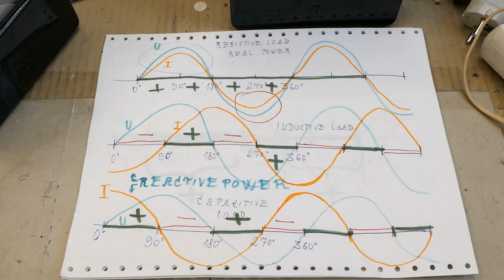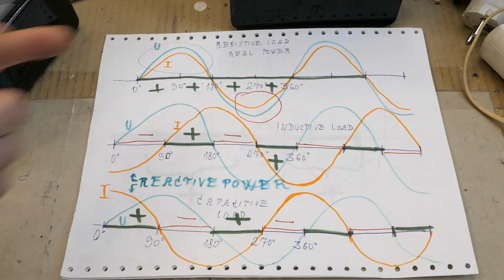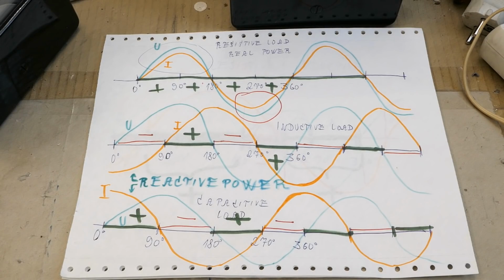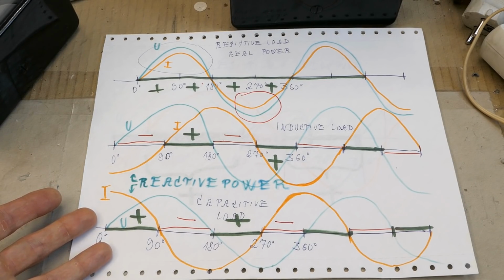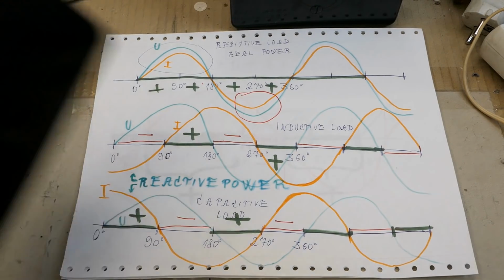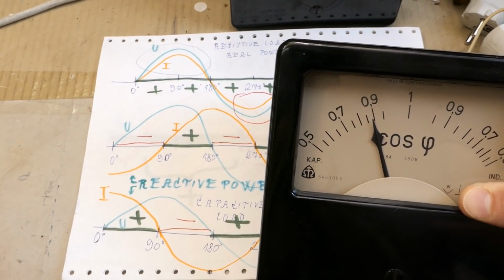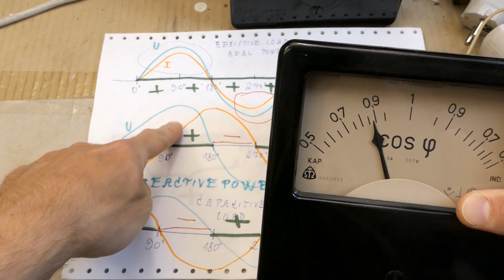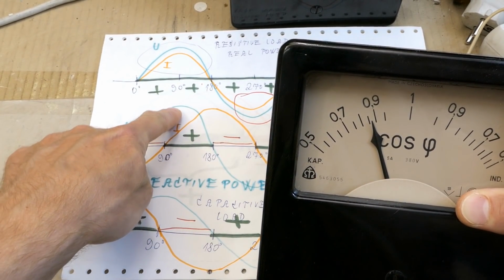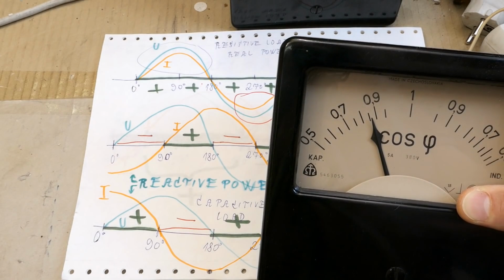It can be, for example, a power supply with a good power factor correction, or a properly corrected inductive load, which has the right amount of compensation, using the right capacitance of a compensation capacitor. For example, a well-compensated motor, or inductive fluorescent fixture, or discharge lamp fixture, or a capacitive load with the right compensation inductor. But anyway, these power factor meters are measuring the power factor based on how much the current is shifted in reference to the voltage and which way.